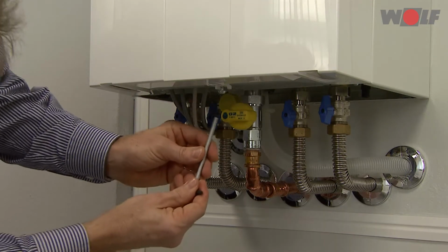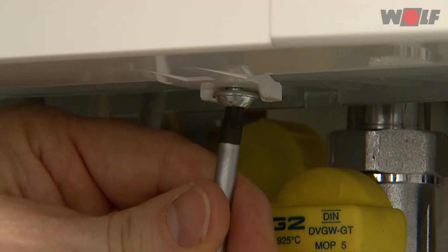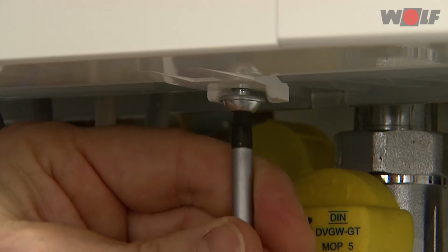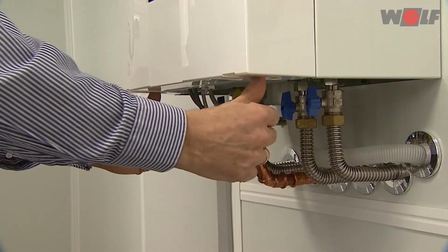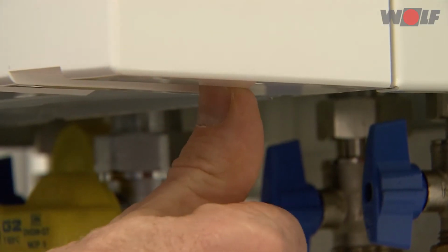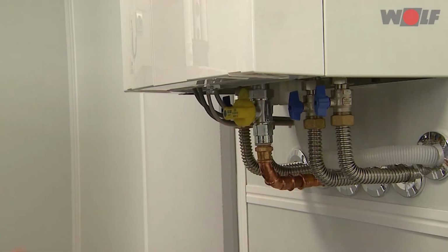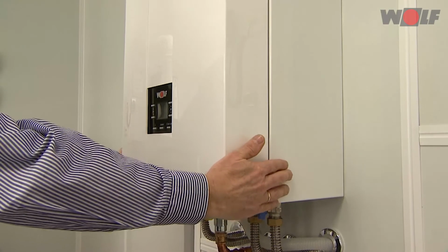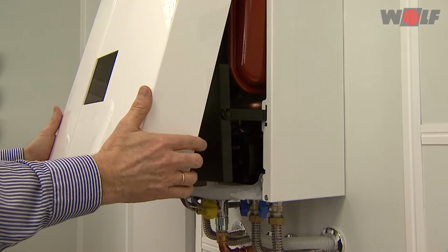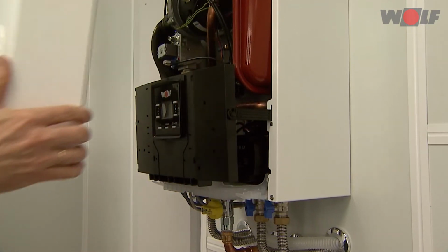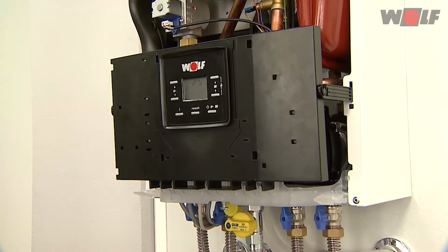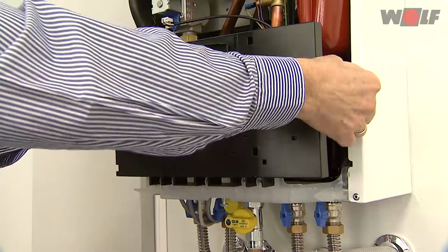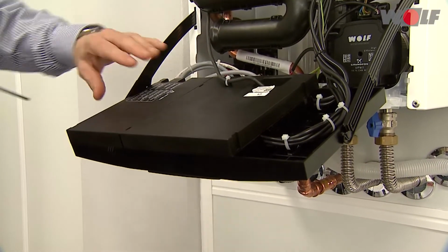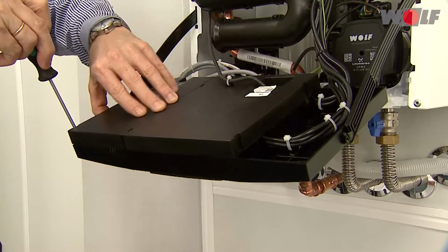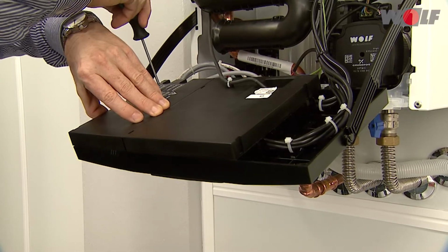Removing the front casing. First undo the central screw at the bottom of the front casing. Push in the two locking hooks at the bottom left and right and pull the casing forwards. Lift the front casing upwards to release and remove it. Opening the control unit. Push the retaining bracket on the casing upwards and pivot the control unit forwards. Open the control unit back. Open the control unit cover using a screwdriver.